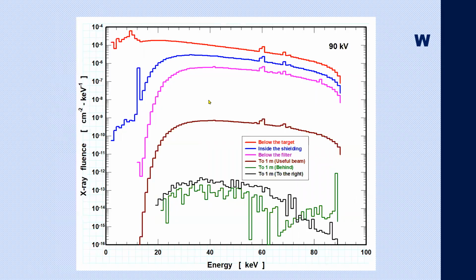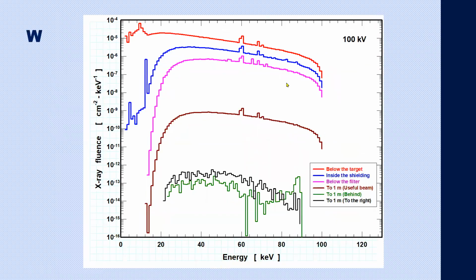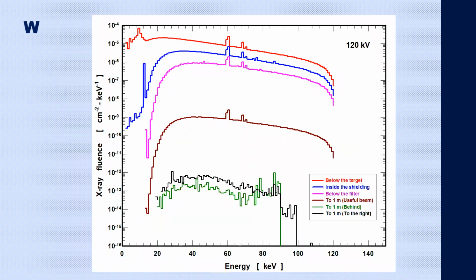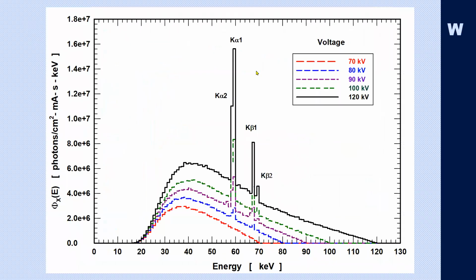You see, we have the same trend, the same tendency, and we notice that the discrete part of the spectrum begins to be more relevant as the voltage is increased to 100 and 120 kilovolts. Now, allow me to show you the spectrum in another fashion. Instead of using logarithmic scale, I'm using here linear scale, and you can see how changing the voltage changes the shape of the spectra, and as the voltage is increased, the discrete components become more important.